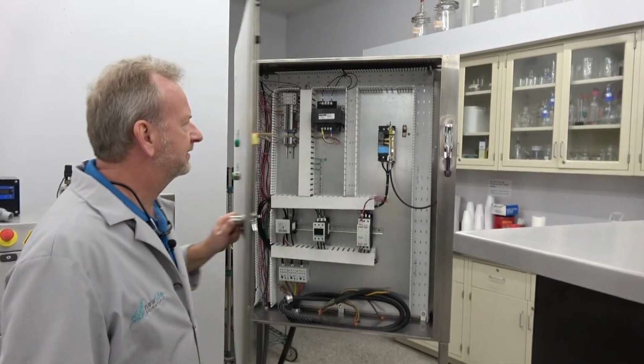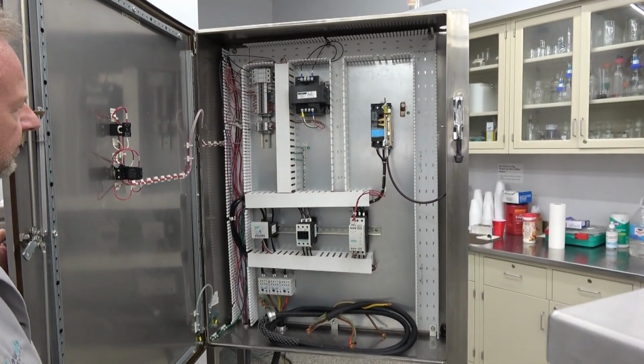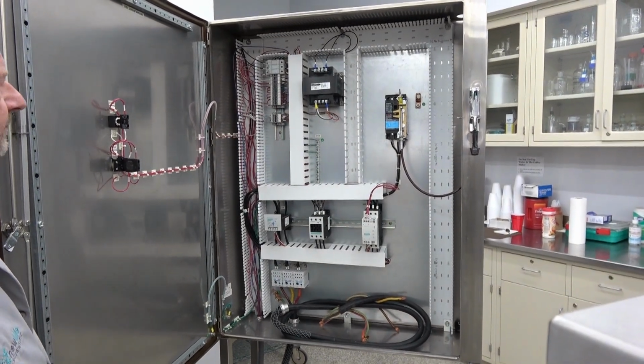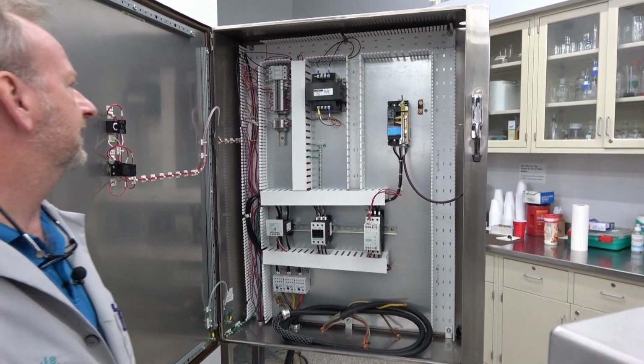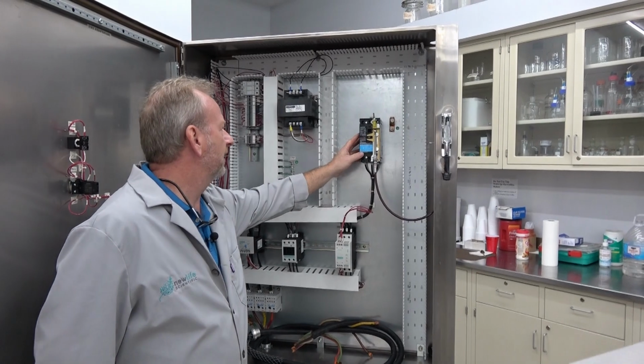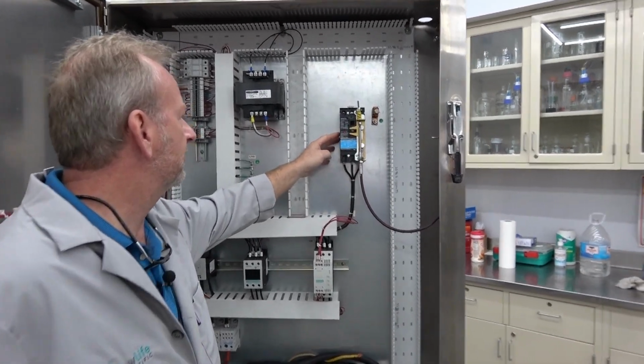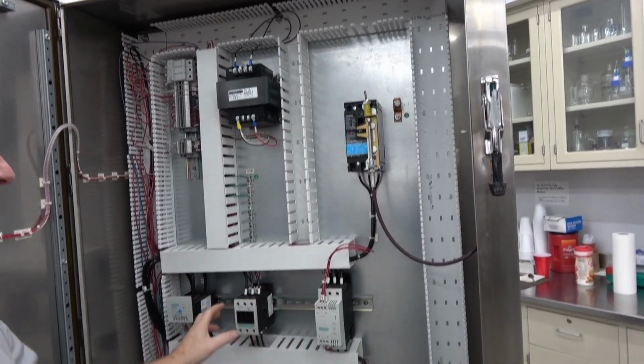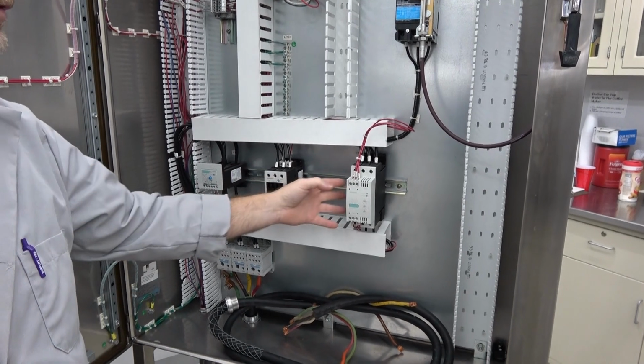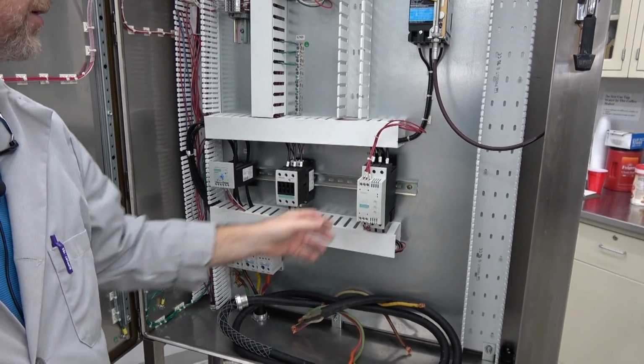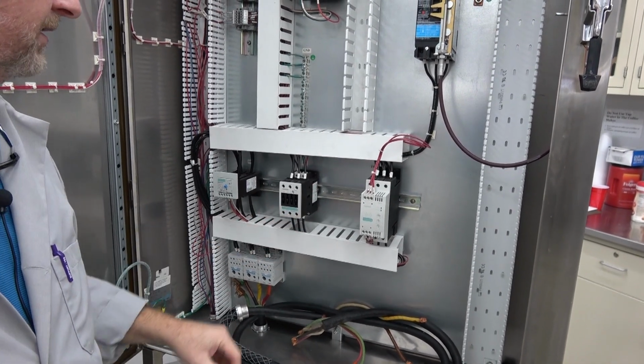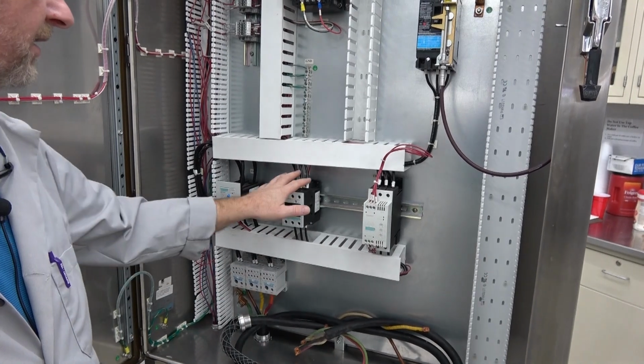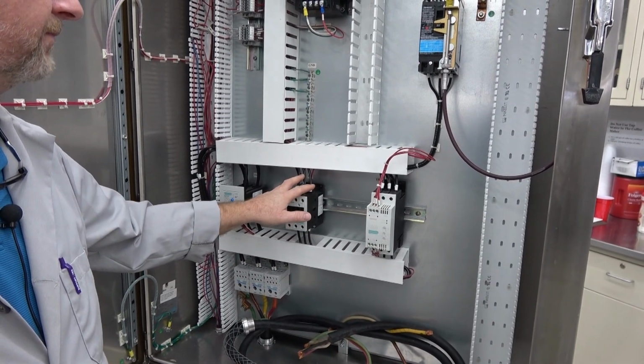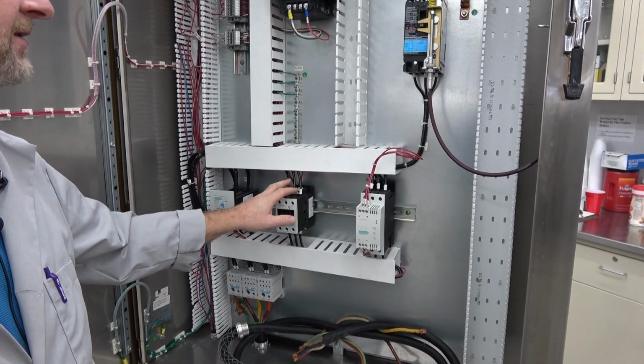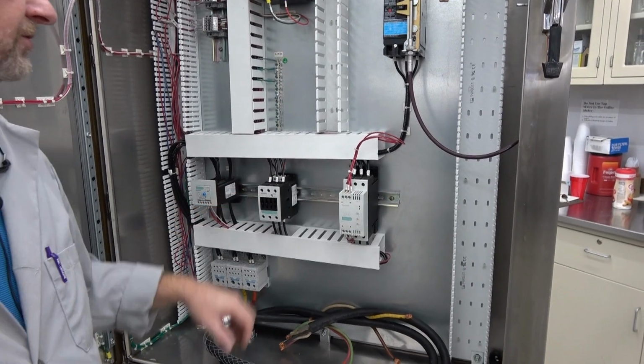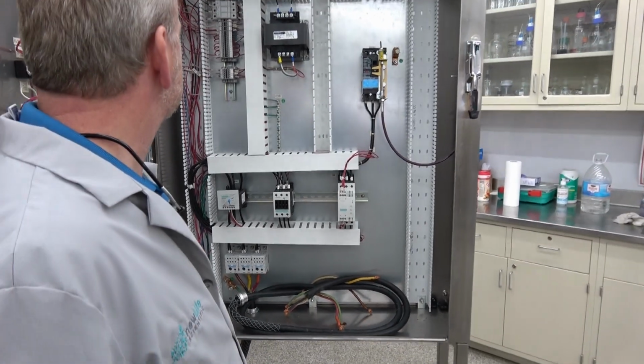Again, say a customer doesn't have access to high voltage - we could easily put in a couple things that would need to be changed. The breaker size would need to be increased to go with low voltage, and your starters, both the primary and the soft starter here, would need to be bumped up, along with the wiring to a higher size. So those are some of the things we can assist with.